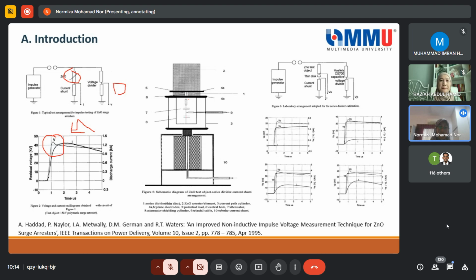So the way they minimize it, of course, they do this arrangement where the test loop is placed here, and then they connect the thin disk. The thin disk represents the divider, but connected in series. So they have this in series, and then this is another divider. They connect it in parallel, so that one divider is connected in series, defined as S, and the divider here is connected in parallel, which we define as P. Then they compare. So this is what we call a calibration test. Calibration means you want to see which measuring device is better, more accurate, or more superior than the other device. So in this case, you can see that this is the parallel, similar to what you've seen before, which has the spike. But when you have the series, then there is no spike. It means that the inductive effect can be reduced even further.